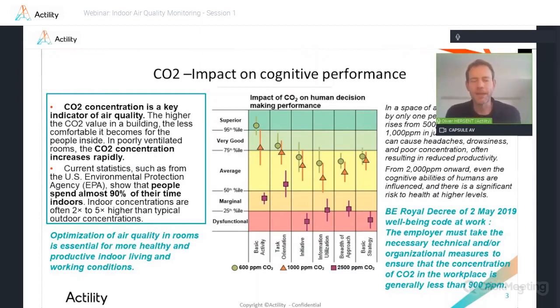And out of curiosity, in my office, I have a CO2 meter. And after receiving a couple of people, just having a 1 hour meeting with 3 people in the office, you can reach 2,000, 2,500 ppm very, very easily. And what this chart shows is that your cognitive performance is really badly impacted, negatively impacted by high ppm, high concentration of CO2 in the room.